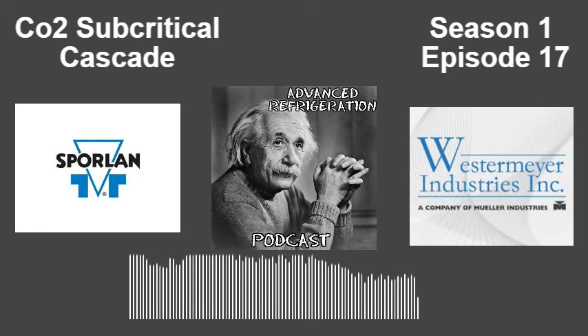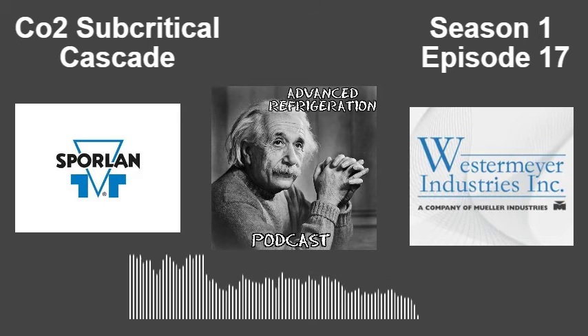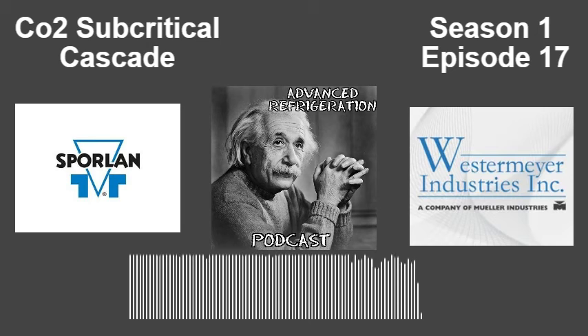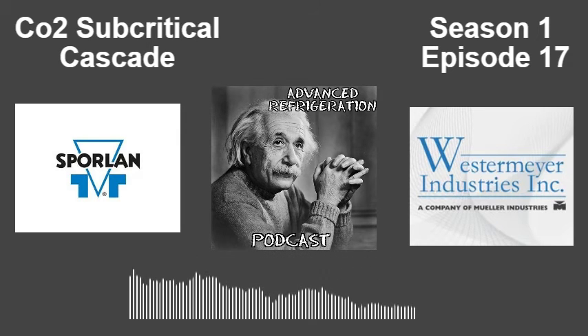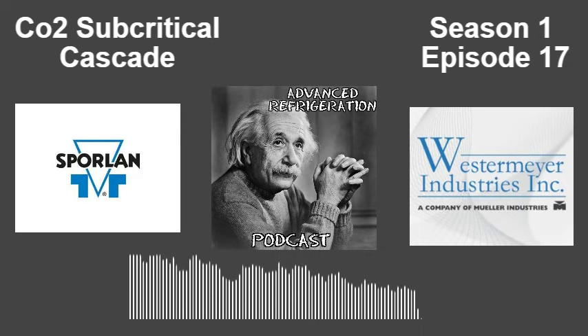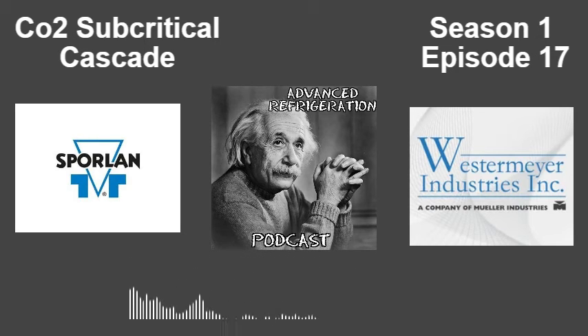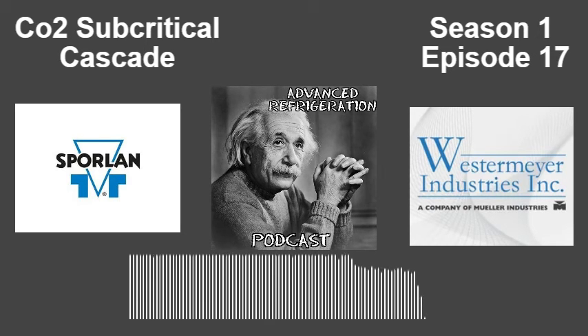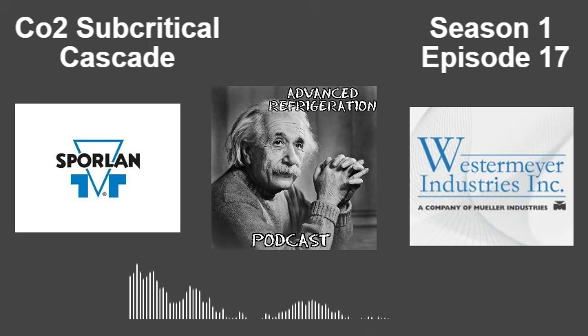Also, about having all these electronic valves, especially if they're bipolar valves, you want to probably reset them at least once a week. You can do this easily with a time schedule. Basically, whenever it hits X time on this day, give it a closure command to shut down. If you have 3 heat exchangers, you're obviously not going to turn off all 3 heat exchangers at the same time. Stagger them by about 15 minutes to a half an hour and let it actually come back down in temperature, because you're basically going to cause that pressure to go up a little bit higher.